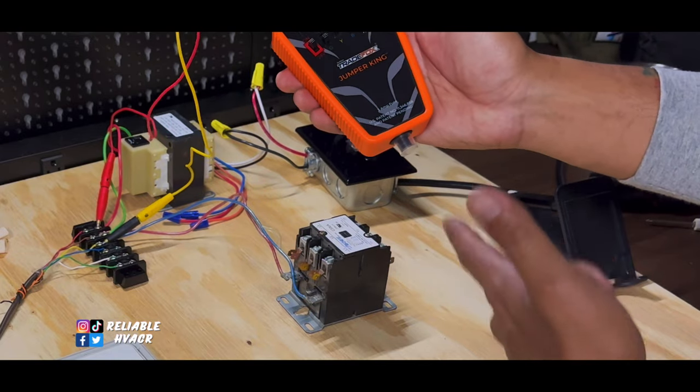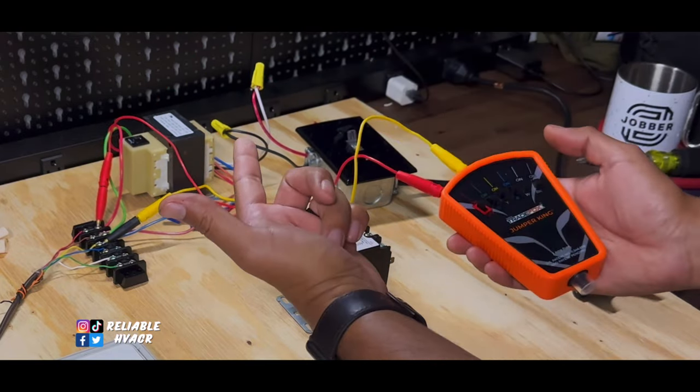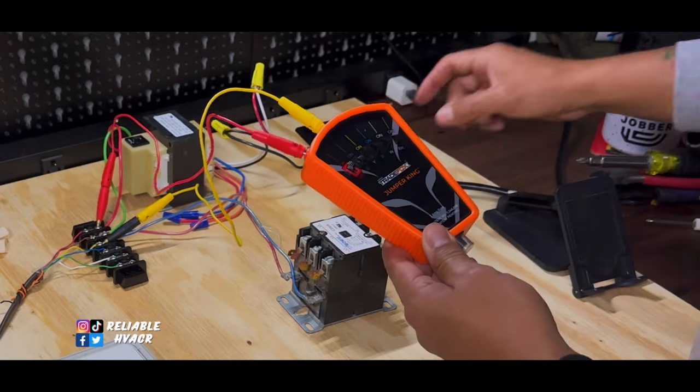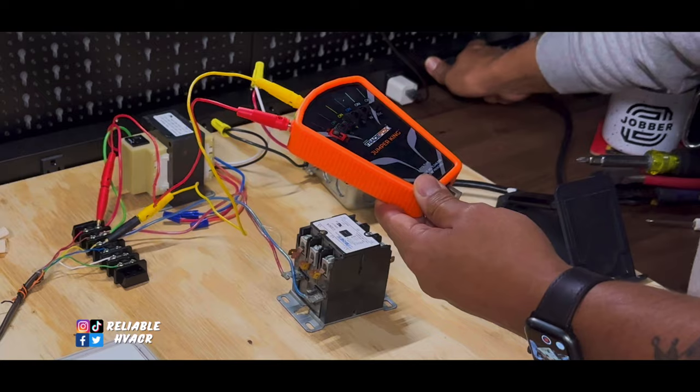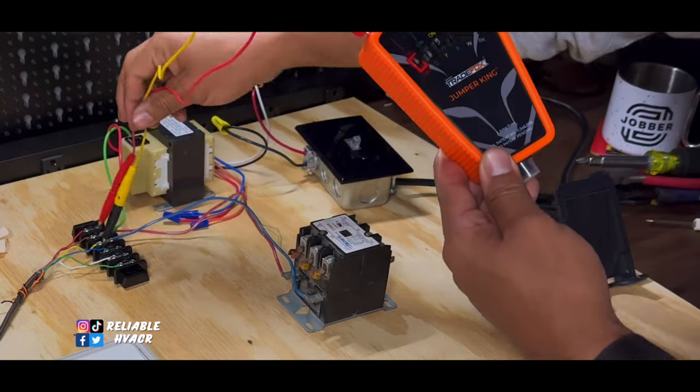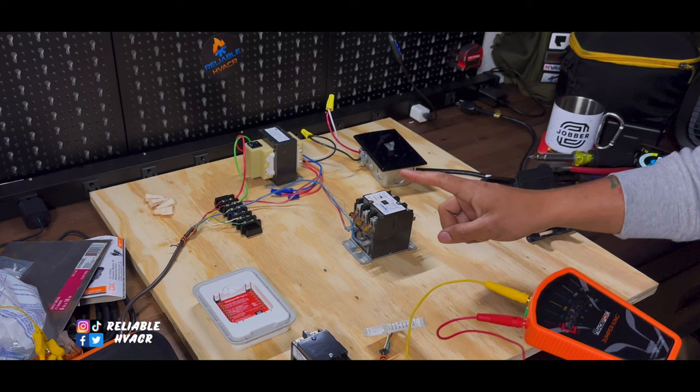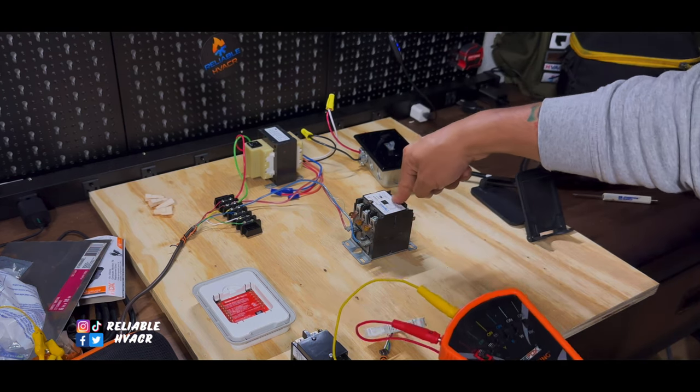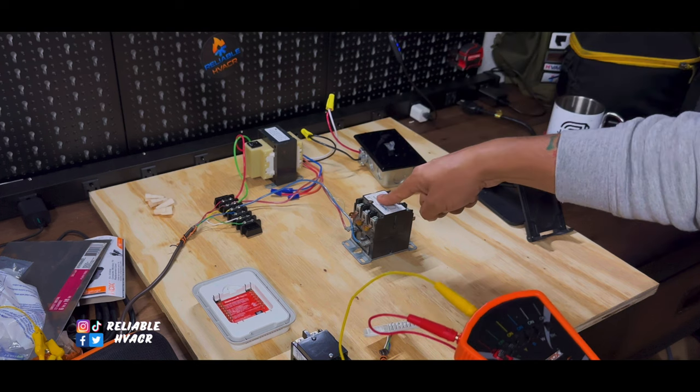Now, the Jumper King tripped. So, this tripped before the transformer, because I'm directly hooked on. So, if you have an issue like this, when I went to this unit, there were, there's going to be three contactors. There's going to be one for each compressor. It was a two-stage, and there's going to be one for the blower motor.